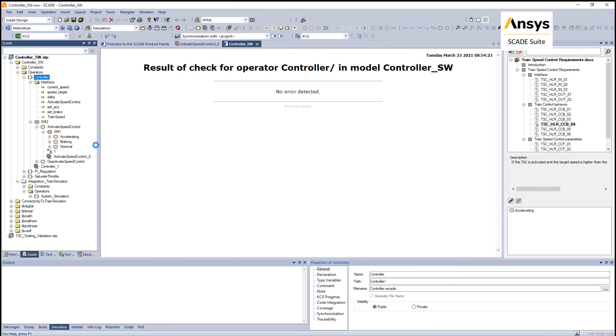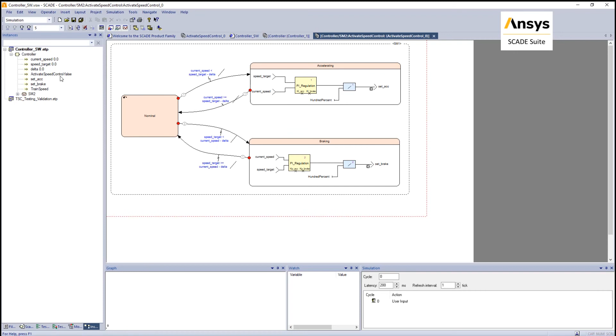The next step in our demo is to run the simulation of the controller using the SCADE Suite simulator environment. SCADE Suite does not distinguish between the model and the code, and you are running the simulation on top of the code. It's offering you an interactive environment where you can set the inputs to check the outputs values. Let's run the simulation and activate the controller. If we set the target speed to a higher value than the current speed, we will see that the system is passing directly into the acceleration phase.